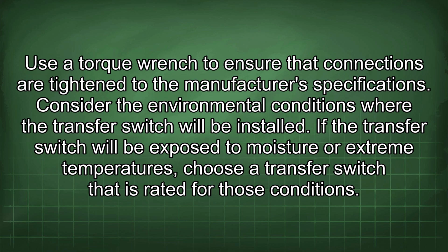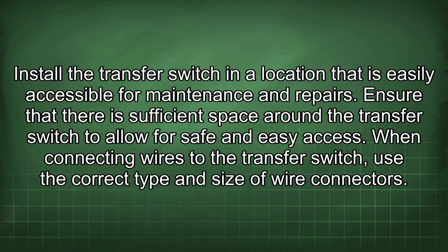Consider the environmental conditions where the transfer switch will be installed. If the transfer switch will be exposed to moisture or extreme temperatures, choose a transfer switch that is rated for those conditions. Install the transfer switch in a location that is easily accessible for maintenance and repairs. Ensure that there is sufficient space around the transfer switch to allow for safe and easy access.